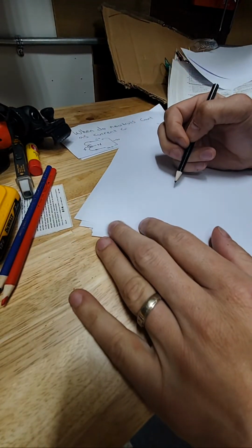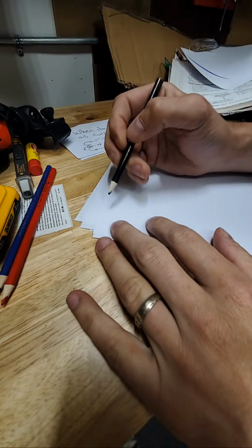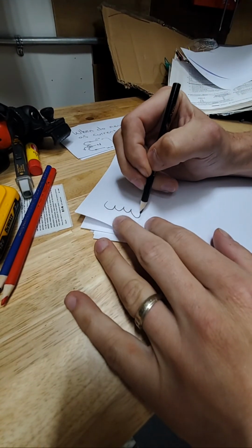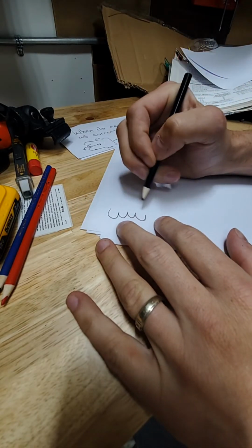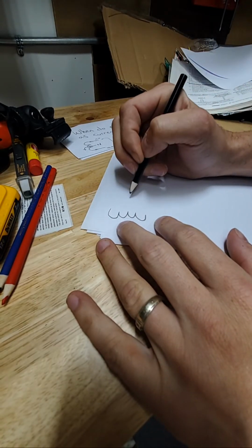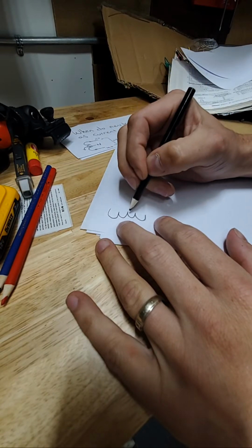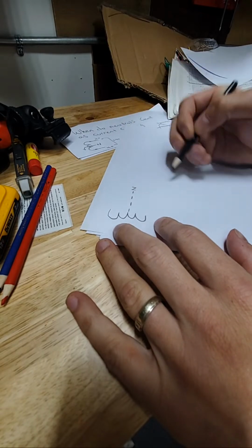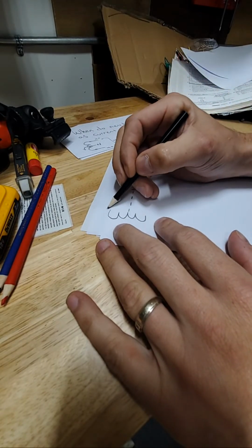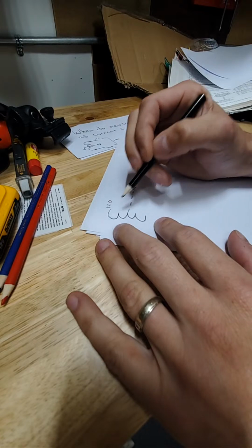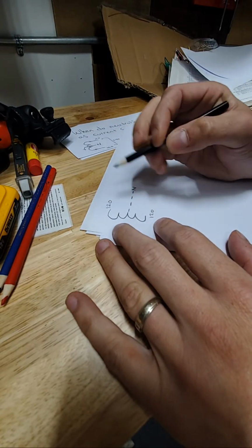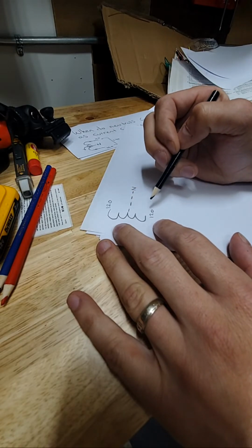We're going to draw a single phase first. So it's going to look like this. This is going to be the transformer windings, if you will. It's not A and B, because this is for single phase. You've got a center tap, which is your neutral. This is the neutral. And from this point here, you get 120 on a leg, and here you get 120. You don't really have A and B on a single phase at your house. So we can even draw that in red.